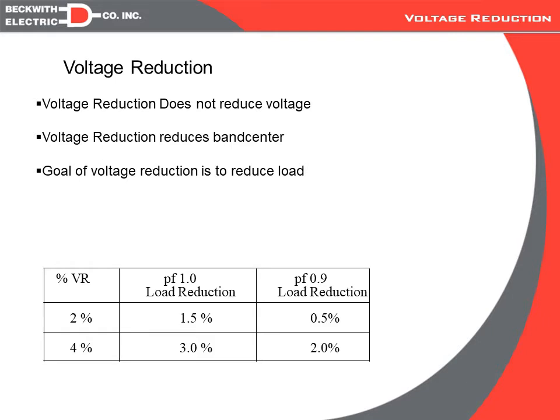So, the purpose of voltage reduction is ultimately to reduce load. And the closer to unity power factor we are, the more load we can reduce as we reduce the voltage. This slide shows a study that I believe was done by EPRI a few years back, and it indicated that for every 4% of voltage drop, you'd get about 3% of load reduction at unity power factor, and that would go down to about 2% of load reduction if the power factor were 0.9 lagging. So, the goal of voltage reduction is to reduce load, either full-time or on a demand basis when needed.